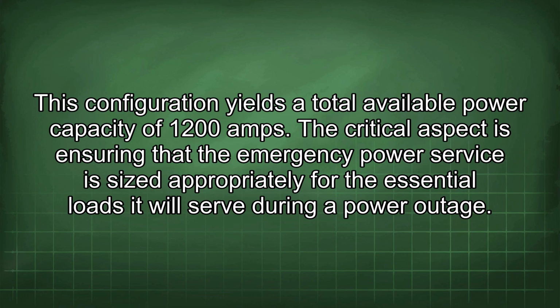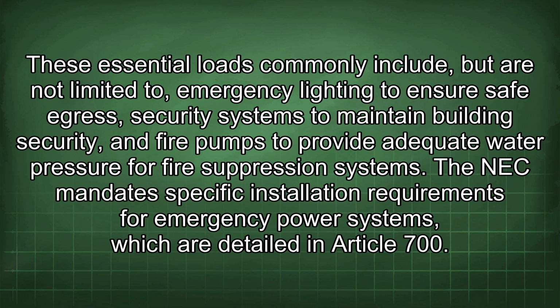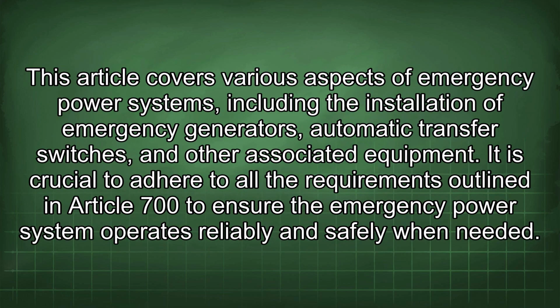The critical aspect is ensuring that the emergency power service is sized appropriately for the essential loads it will serve during a power outage. These essential loads commonly include, but are not limited to, emergency lighting to ensure safe egress, security systems to maintain building security, and fire pumps to provide adequate water pressure for fire suppression systems. The NEC mandates specific installation requirements for emergency power systems, which are detailed in Article 700. This article covers various aspects of emergency power systems, including the installation of emergency generators, automatic transfer switches, and other associated equipment. It is crucial to adhere to all the requirements outlined in Article 700 to ensure the emergency power system operates reliably and safely when needed.